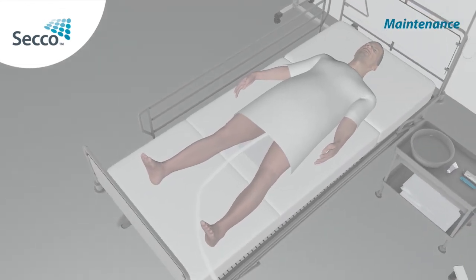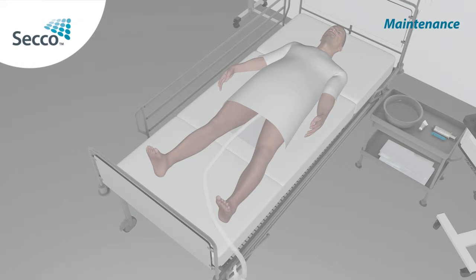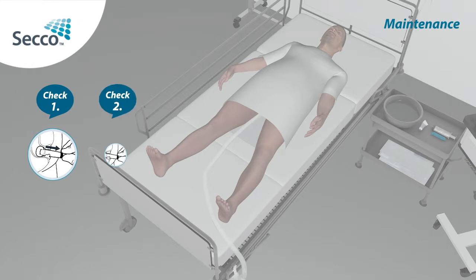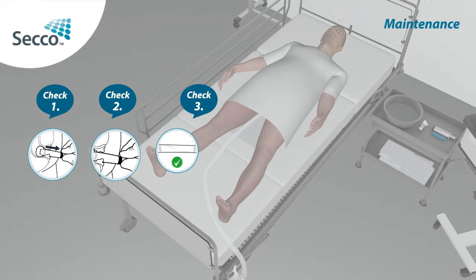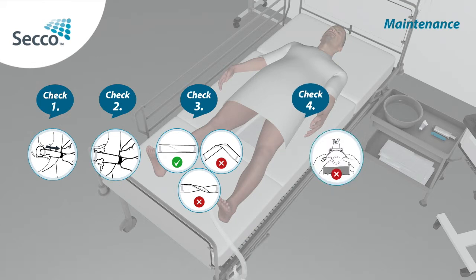Maintenance. The following checks need to be made several times per day. Check that the inflation cuff is correctly positioned against the rectal floor and cuff volume is correct. Check that the black line on the catheter tube is visible. Check that the catheter tube is flowing freely and is not kinked or obstructed by the patient's body or other medical equipment. Check that the collection bag does not need to be replaced.